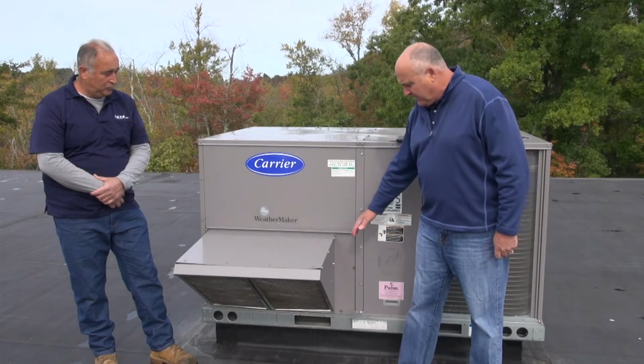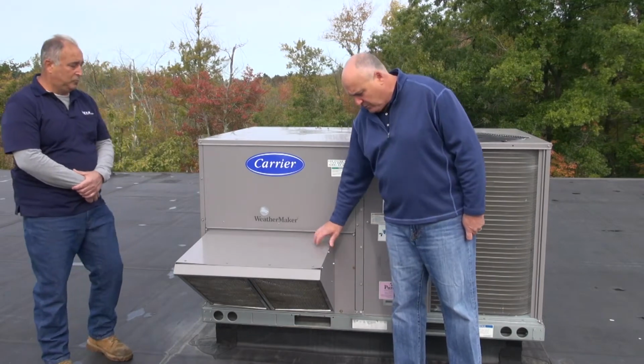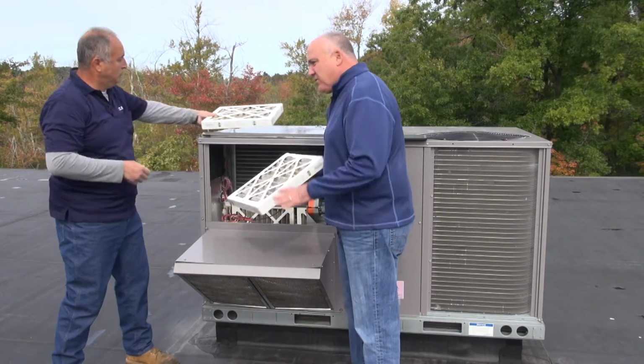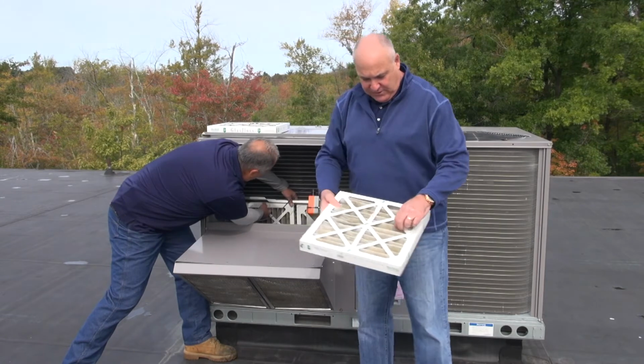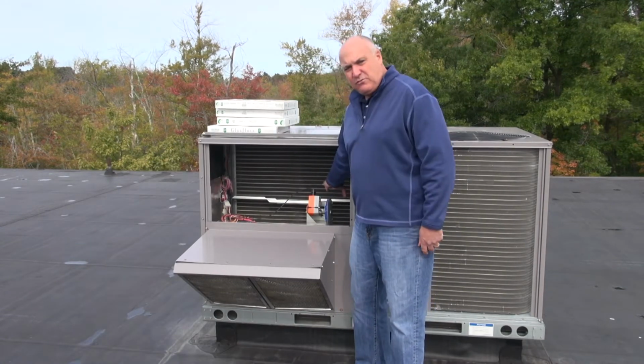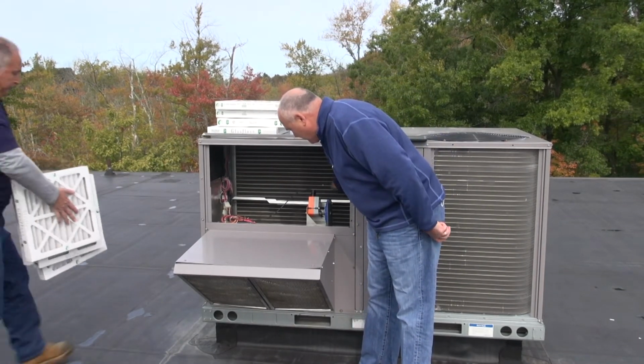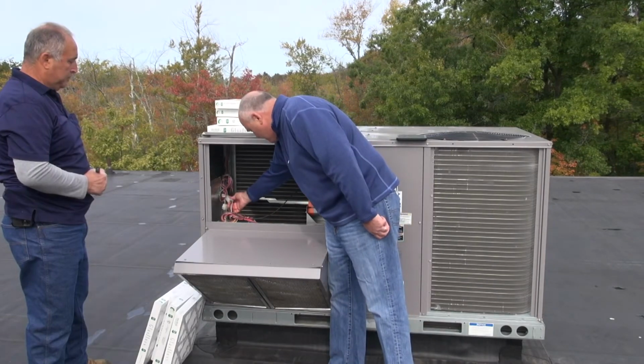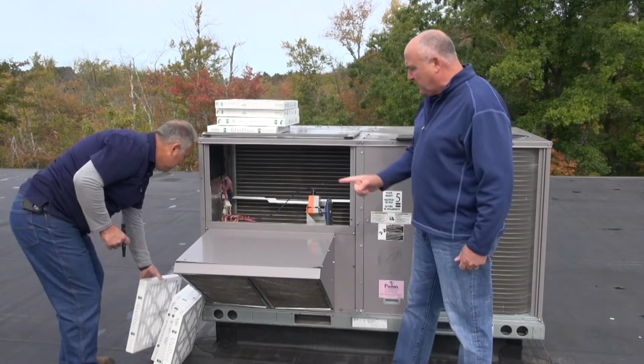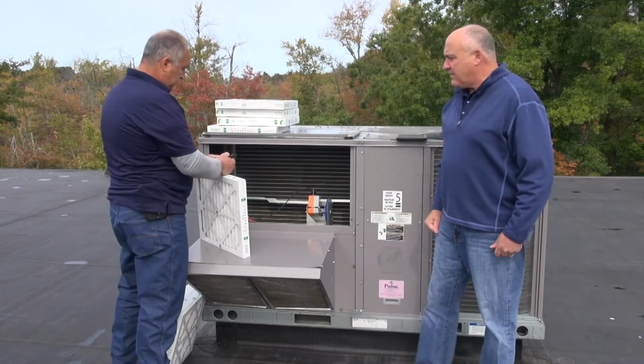The next section we inspect is the filter section and the economizer. We replace the filters, which get covered with pollen and dirt. At the same time, we inspect the evaporator coil and brush clean it if needed. Wiring is also inspected, and the new filters are dated, so we'll always know when they were last replaced.